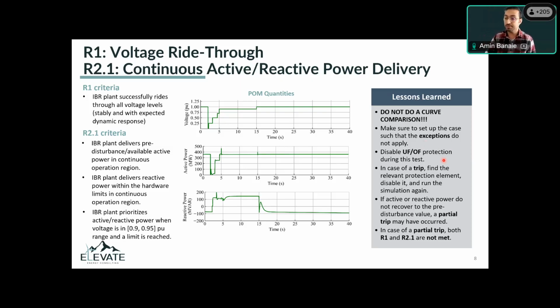The other thing is that we've seen that the under frequency and over frequency elements trip during this test. And the reason is that the PSSE and PSLF engines, specifically, are not able to calculate frequency when the voltage goes to 0. And they cause an unrealistic under frequency and over frequency tripping. So to capture that, you may want to disable under frequency and over frequency protection across the plant.